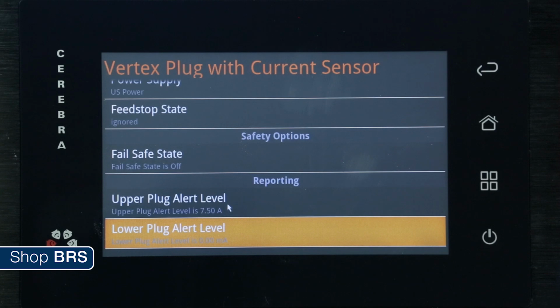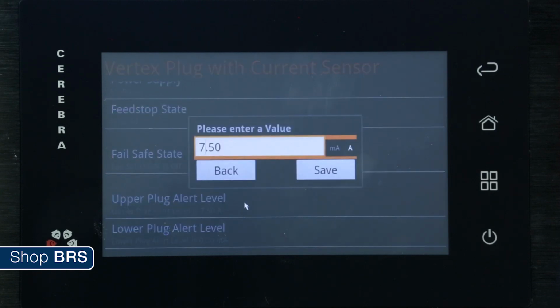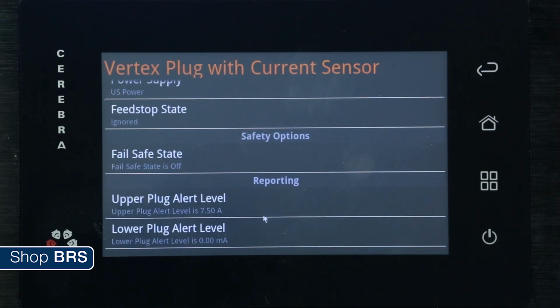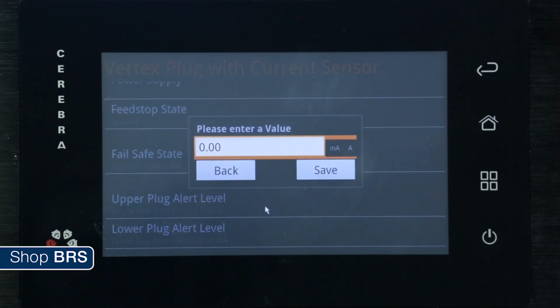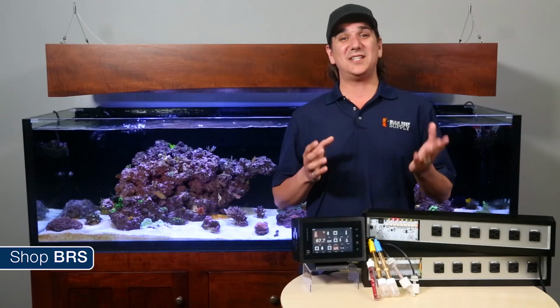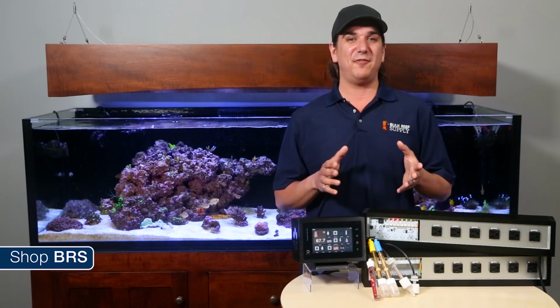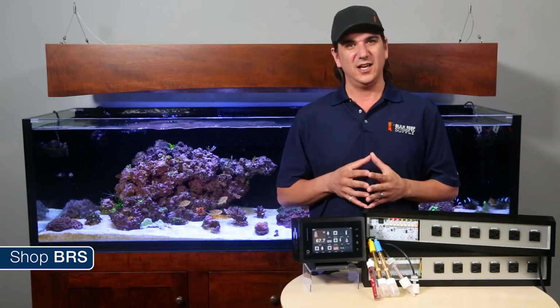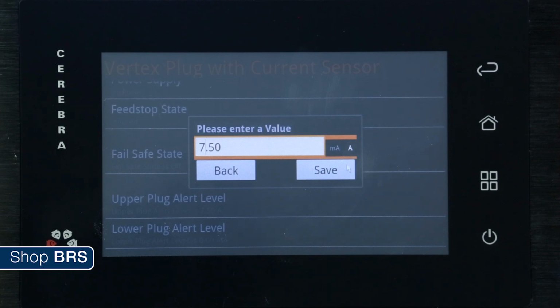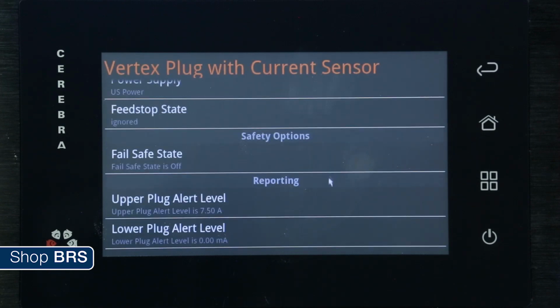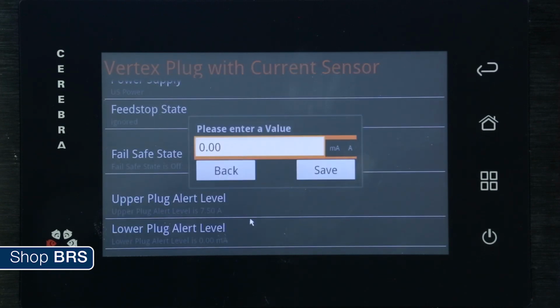The upper and lower alert level are power monitoring settings to send alarms at any time there's an outlet, which is supposed to be on, but it's consuming more than 7.5 amps or 0 milliamps. In both cases, this would be an issue. This will tell us if our dosing pump has somehow failed and no longer turning on. You can, of course, change either one of these values to higher or lower amps or milliamps to best fit the type of equipment you're controlling.